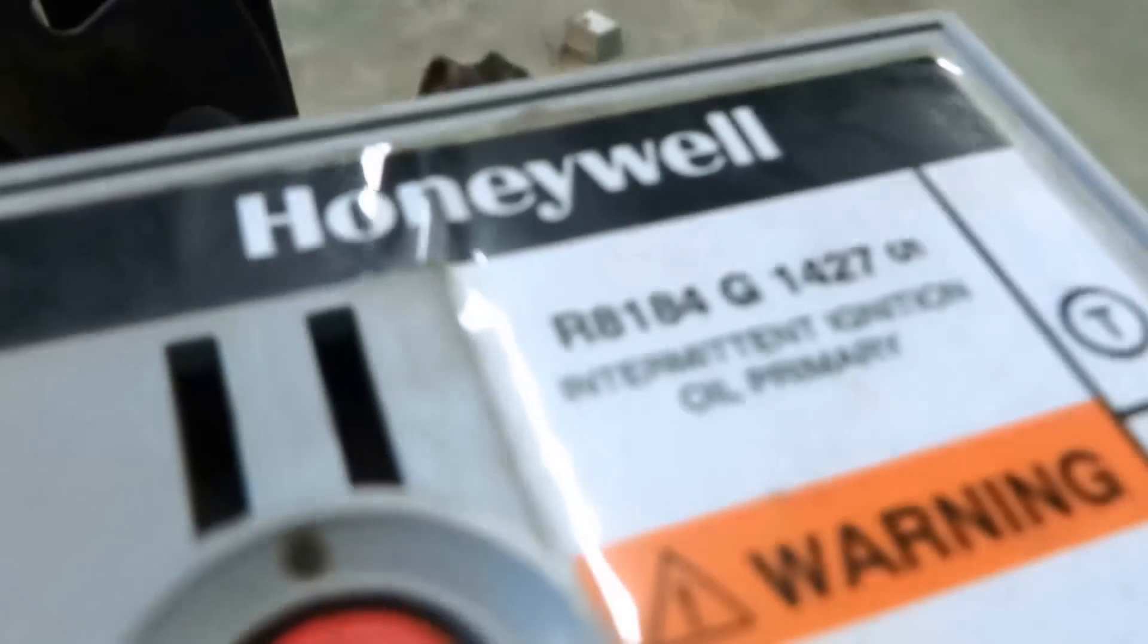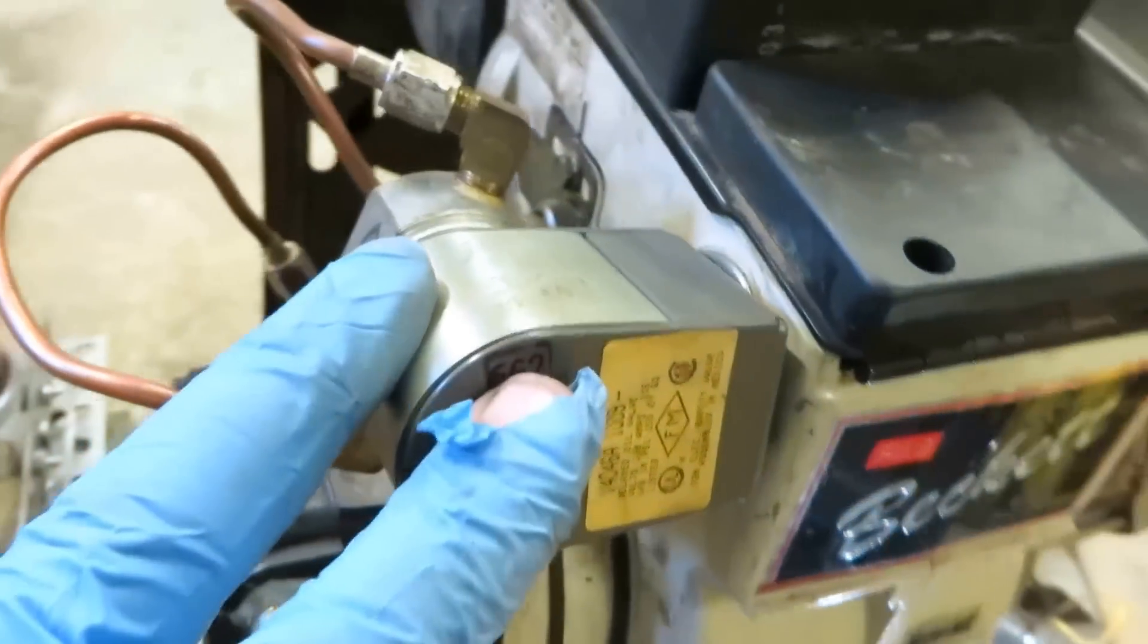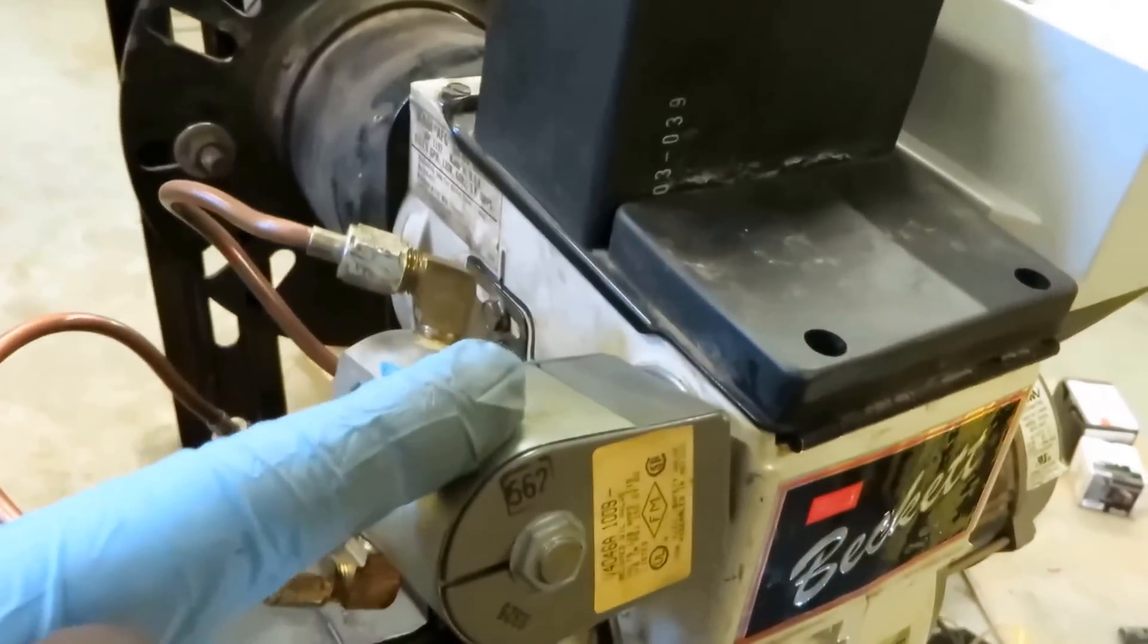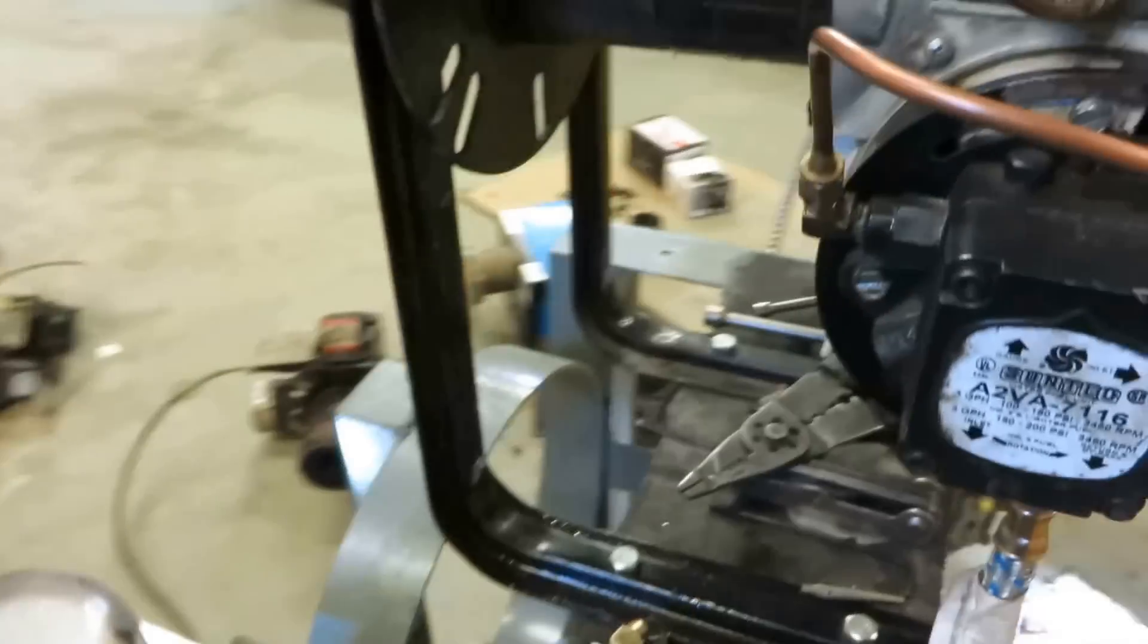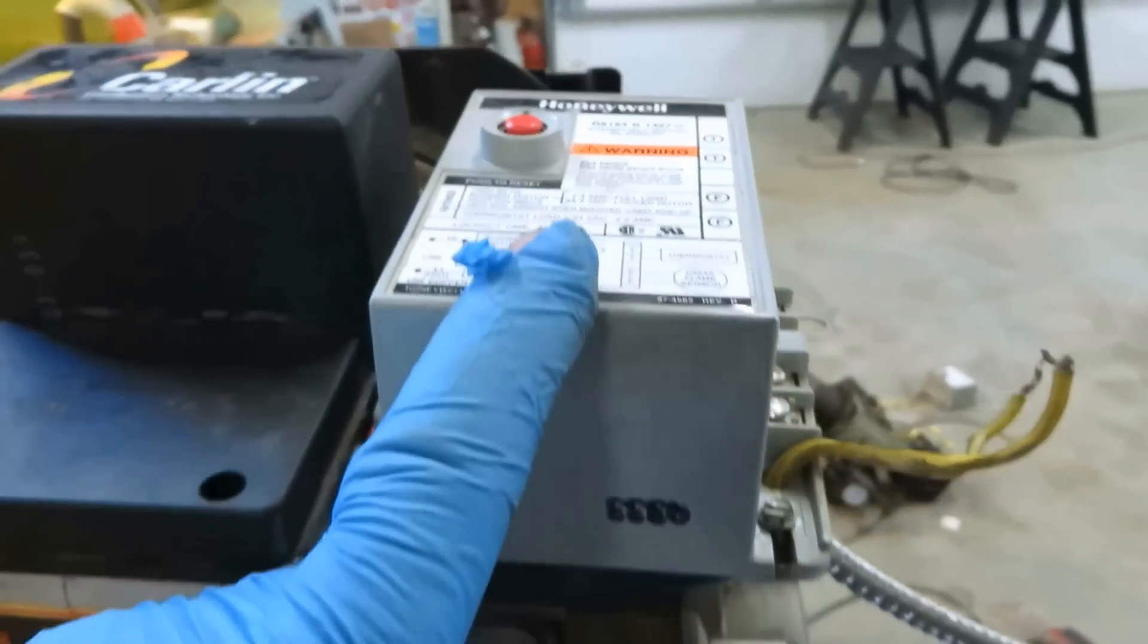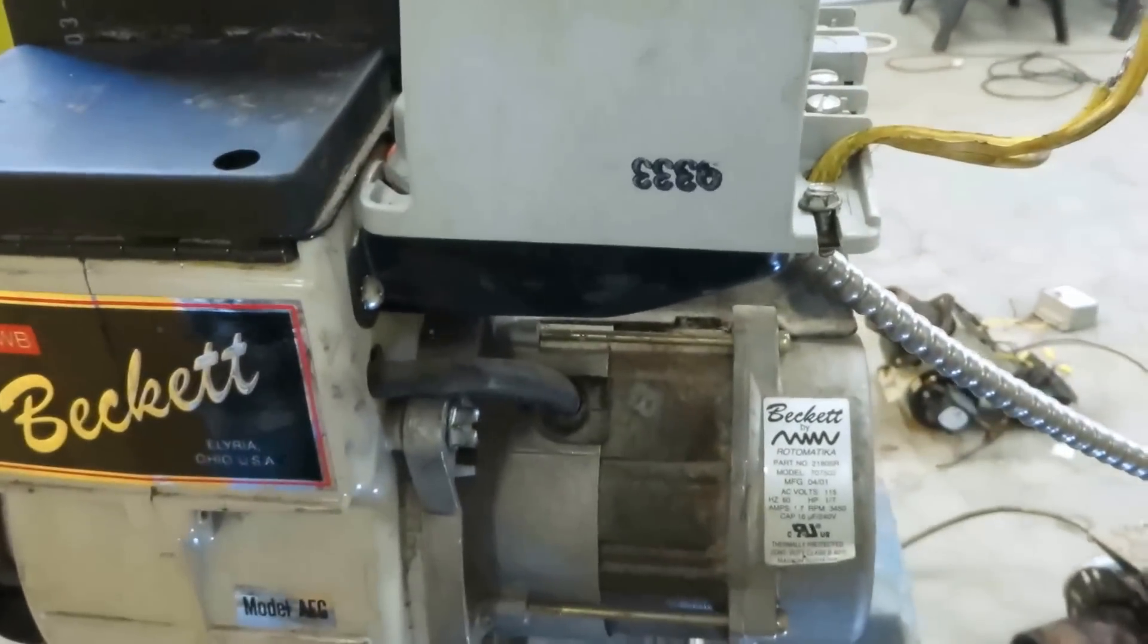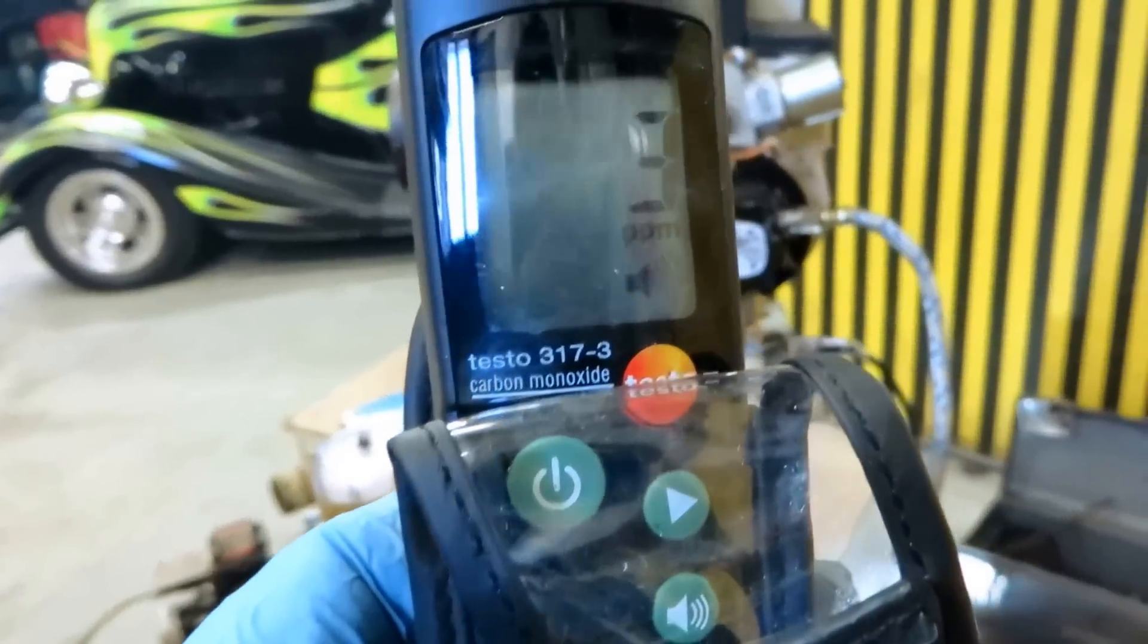All right guys, I got my R8184G hooked up to the delayed oil valve. So it will fire up and there will be a delay on the oil valve. It's got a built in delay on this anyway before it fires. Just won't have a post-purge with this type of control. Just checking my environment here with my carbon monoxide detector. Three parts per million.